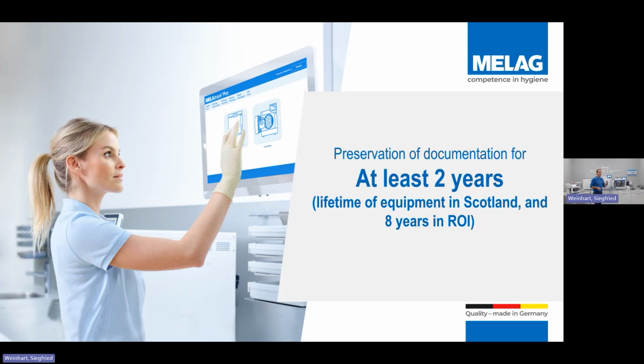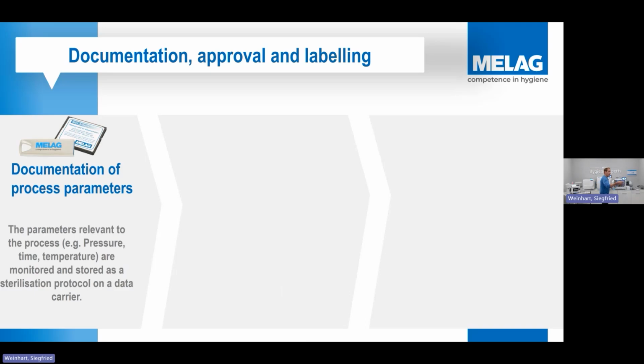Now, how do we record? Many different ways that autoclaves and washer disinfectors can record data now. So some of these you will be familiar with already. First one, documentation using a common USB stick, or it might be using a little CF card, or you might well have a reader that's got an SD card in it. They're all good forms of recording parameters. And what they tend to do with these ones, it fits into the screen, but you might get a little box that your unit sits on with your little SD card in, or it could be a separate unit that the USB stick sits in. And what that's doing is basically recording when you run your S cycle or your B cycle. Everything that would have been put on your traditional printout will be recorded on the data logger.